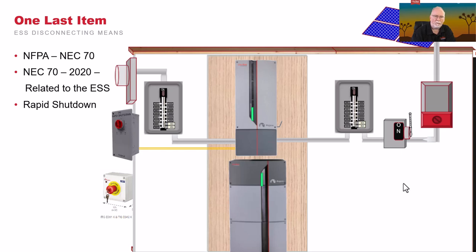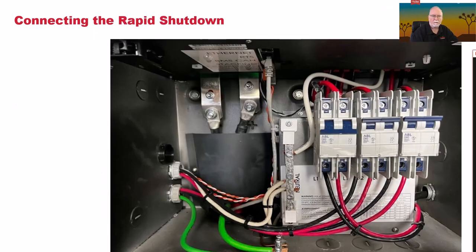If you watch here, what I'm going to do is turn the little knob here, and you'll see my Mojave will go dark. So effectively what this will do, this will drop the grid input and the output breakers, the generator breaker effectively, and shut down the inverter. At this point, you would also probably have to disconnect the grid direct PV shutdown as well. If I turn it back on, everything returns to normal, battery turns back on, inverter turns back on. Make sure everything's operational, close the breaker on the grid direct PV.